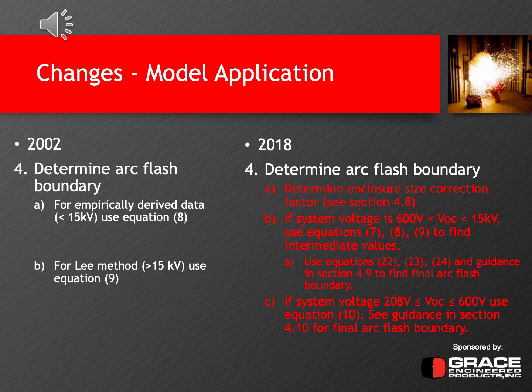In 2018, to determine the arc flash boundary, you need to look into section 4.8, which gives you guidance on the enclosure size correction factor. And then, based on that, you would then perform a calculation. If your system voltage was between 600 volts and 15 kV, you would then use equations 7, 8, and 9 to find those intermediate values. And then you would use equations 22, 23, and 24, and then guidance in section 4.9 to find the final arc flash boundary values. So it's very similar to the incident energy calculations where you need the enclosure size correction factor.